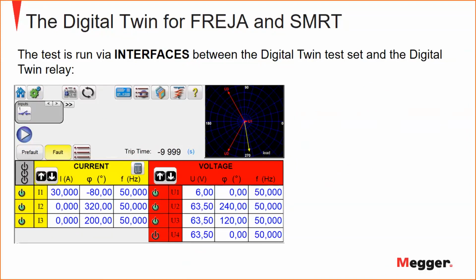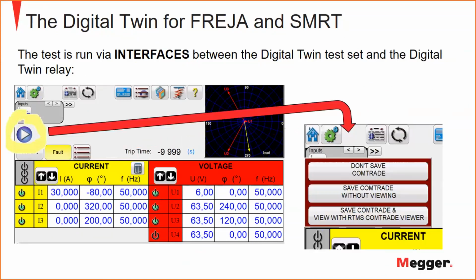How do you want this data in your relay? For the moment, the data is in COMTRADE. So the next step will come soon, but for the moment, data is in COMTRADE. The test runs, and all the samples are generated, all the values are generated like a normal test set, but then at the end, it says, okay, don't save COMTRADE because you did strange stuff, you did the wrong test. Save COMTRADE without viewing, or save COMTRADE with view with the RTMS COMTRADE viewer, so you can have a preview of what we are going to save. This is our output.